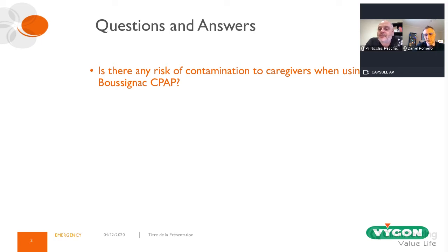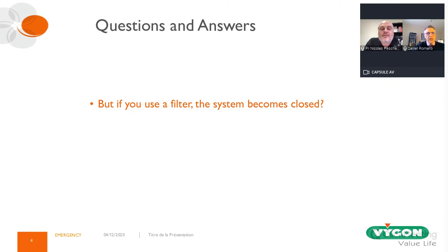Yes, because we have some questions related afterwards. The next one is: but if you use a filter, doesn't the system become closed? So partially no, actually, because the oxygen and air particles are smaller than the diameter of the holes in the filters. The diameters are pretty small, of course, to stop viral particles on the inside part of the filter, but there is no effect on the air and oxygen particles. Okay, no resistance. Okay, very good.